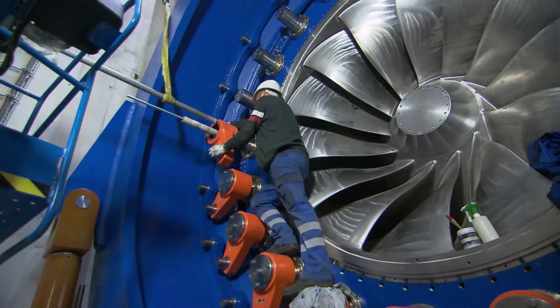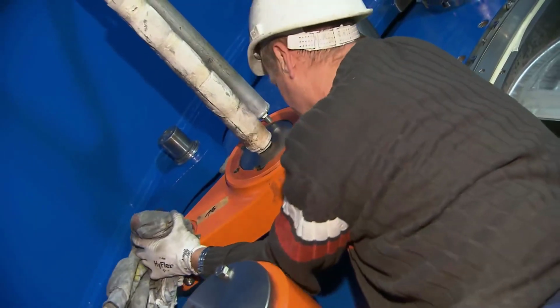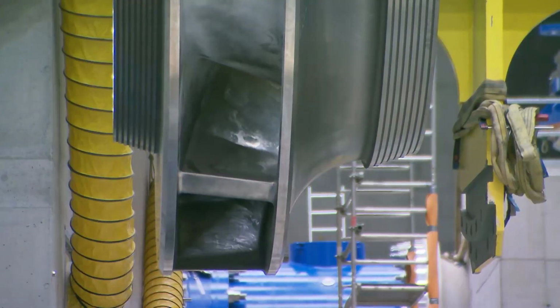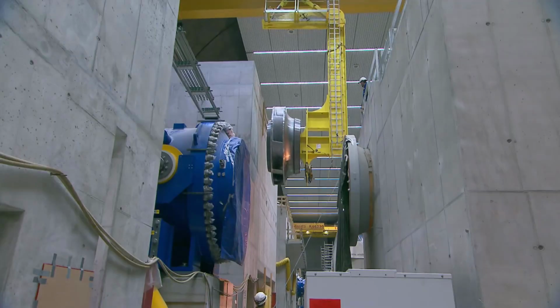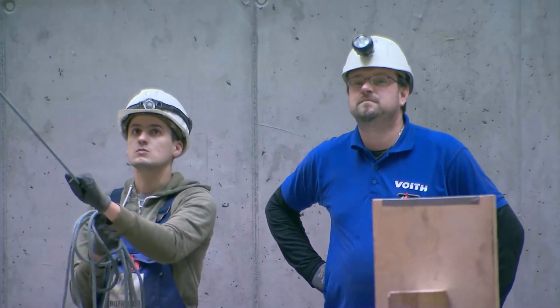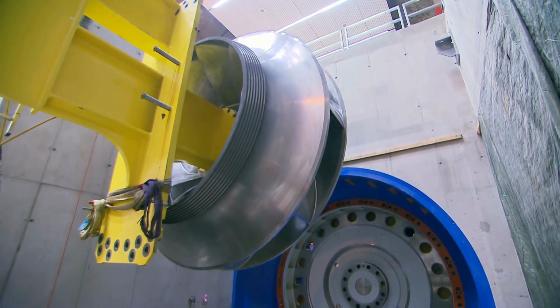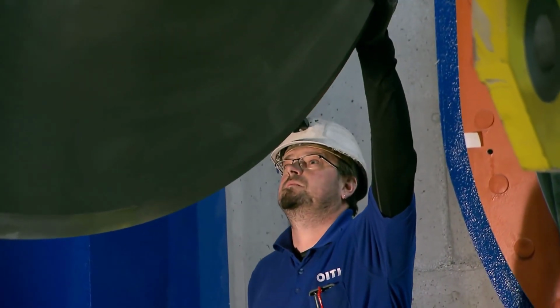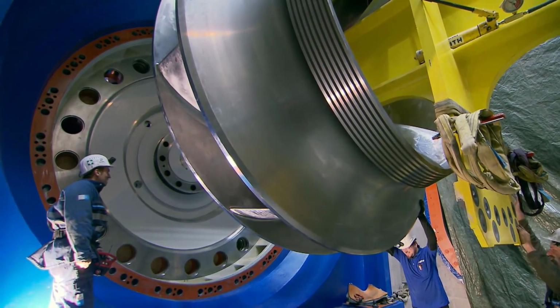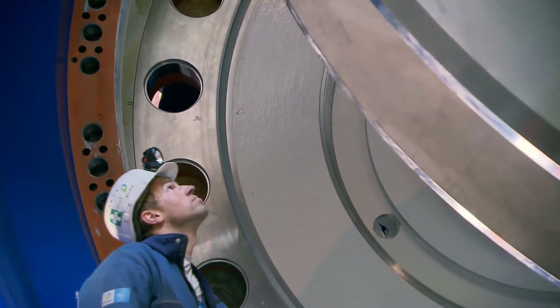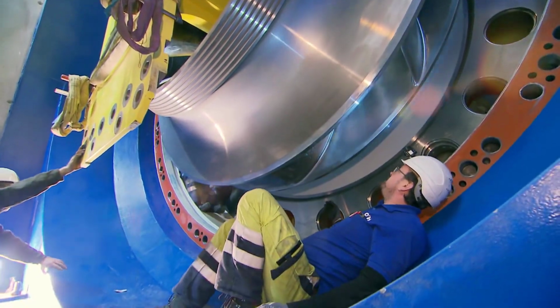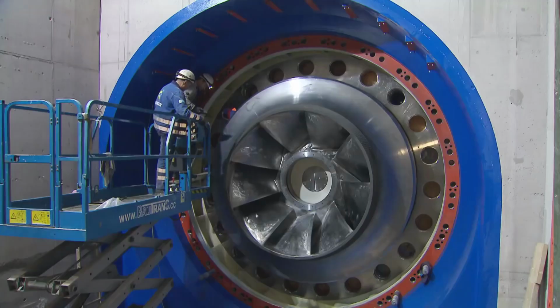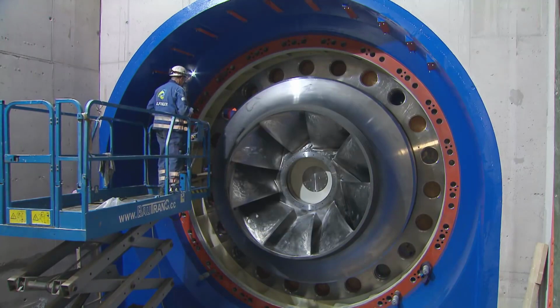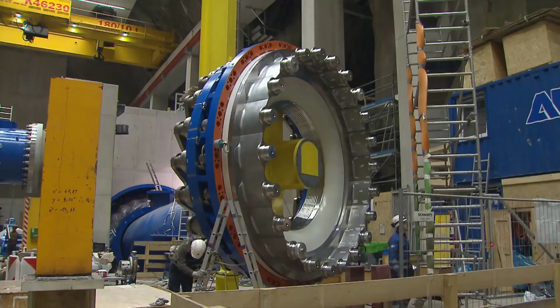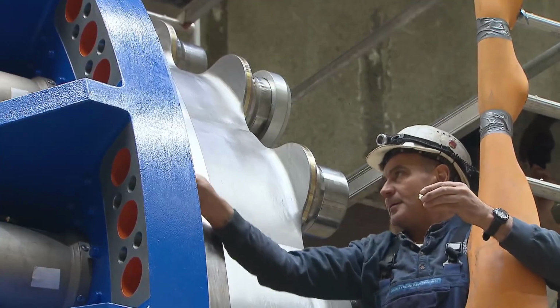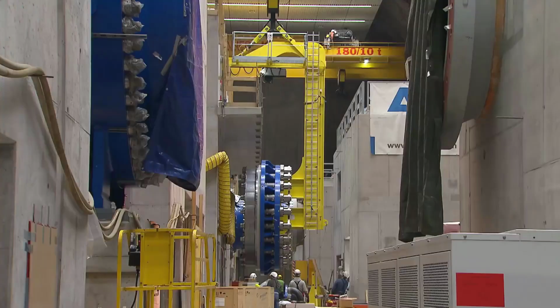The heart of the pump, the impeller, is now being installed. The special crane hook is used again to insert the impeller into the already embedded spiral. The impeller, with a diameter of 3.4 meters and a weight of 19 tons, is one of the largest individual parts of the machine set, and precision is crucial for its exact installation. The final major part of the machine, the pump cover, is then installed. Unlike the turbine, the guide vanes were already assembled with the impeller in the factory, allowing the pump cover to be bolted as a complete unit to the machine set. Screws and nuts are once again used, exceeding normal dimensions.